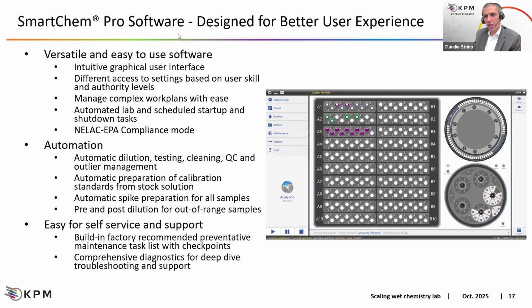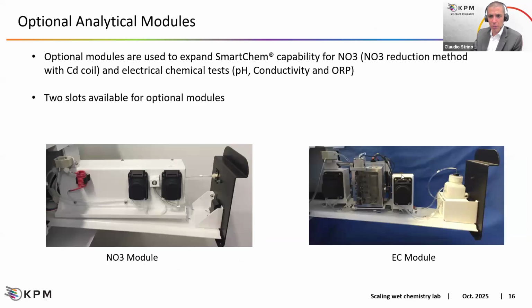No, this is a plus on the SmartChem series. So SmartChem 210, 450, and 600. By default, on the standard configuration, there are no peristaltic pumps. The only peristaltic pumps available are on the 2 optional modules. And in this case, it's very easy, because we just need to unlock the pump, remove the head, remove the whole tubing, put in the new one, put the head of the pump back and close the arch to have the pressure back on the tube. And that's all.